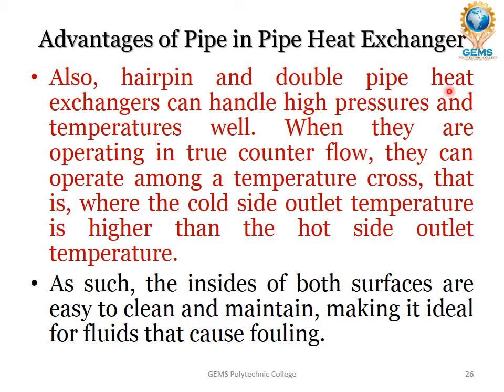Also, hairpin and double pipe heat exchangers can handle high pressures and temperatures well. When they are operating in true counterflow, they can operate among a temperature cross, that is where the cold side outlet temperature is higher than the hot side outlet temperature. As such, the insides of both surfaces are easy to clean and maintain, making it ideal for fluids that cause fouling. So it is easy to clean the inner surface and outer surface, so that we can make it free from the fluids that cause fouling. Fouling means salt, scale formation.